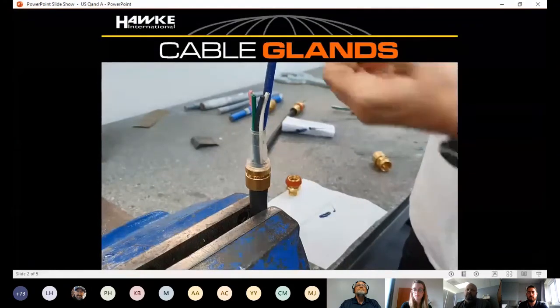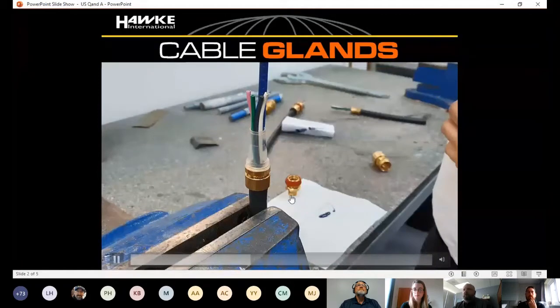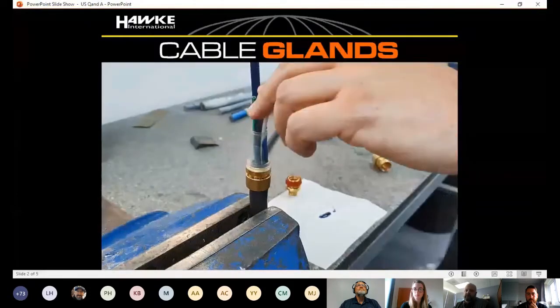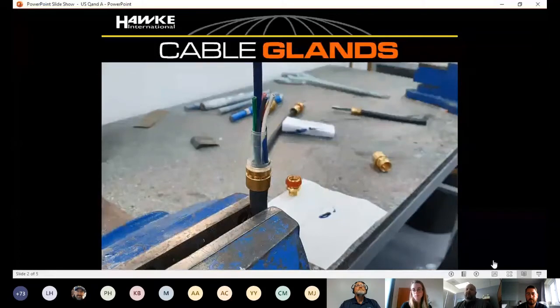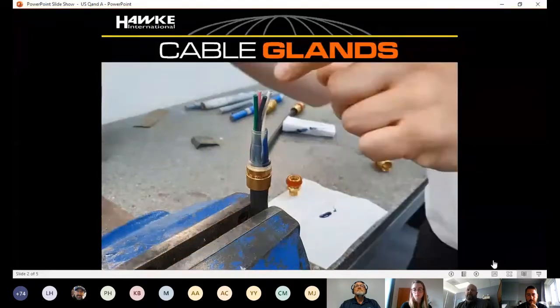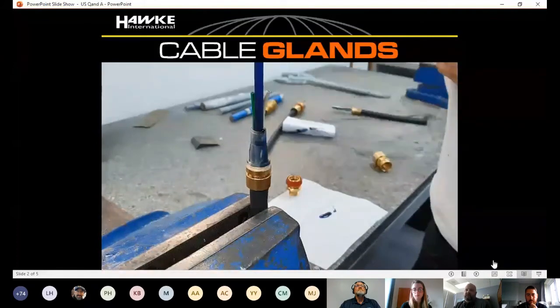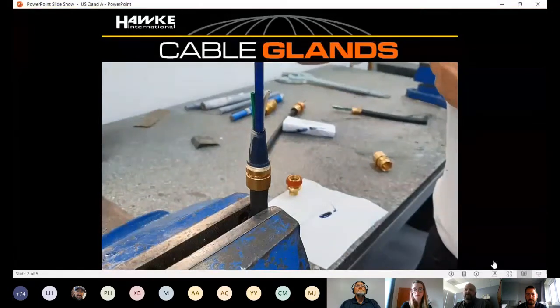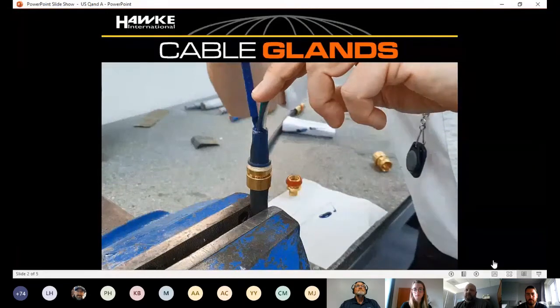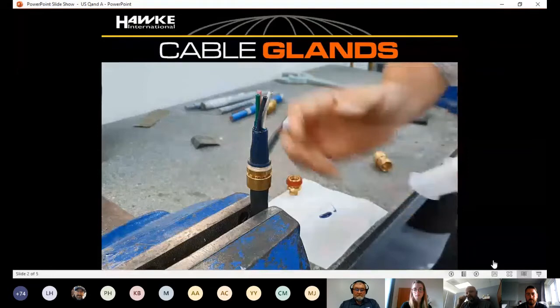With the QSP version, which is your 2-part compound, if you're having to do horizontal installations, then you still have the ability to do that, and you also have the faster curing times. With the injectables, that's going to be about a 30-minute cure time, irrespective of the size, but you will have to make sure that you allow that to cure in a vertical position. You're still going to get your faster cure times. And the biggest benefit to all this is that they use the exact same compound pot, the clear pot. So with both resins, you're going to get your full inspectability. You also get your faster curing times, and you'll be able to manipulate it. As you can see with the video that's going on right now, the silicone pot is flexible.